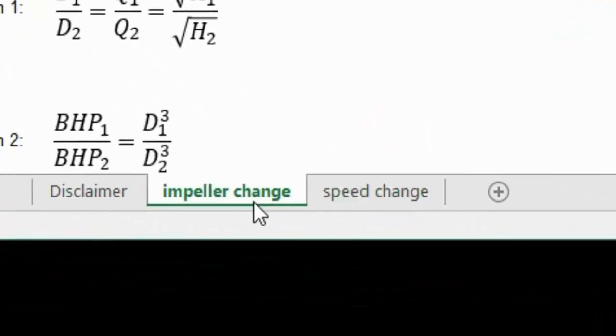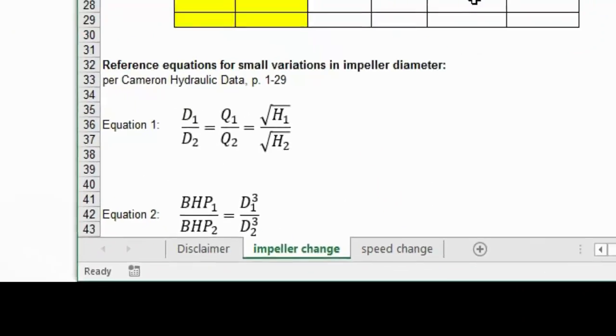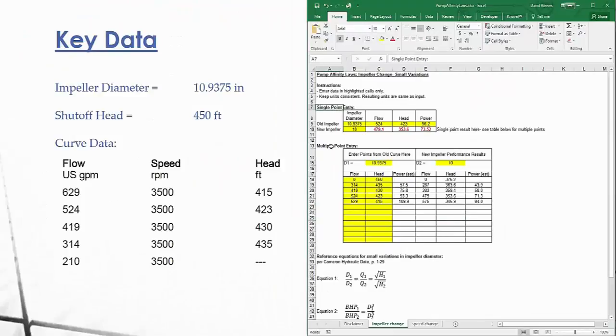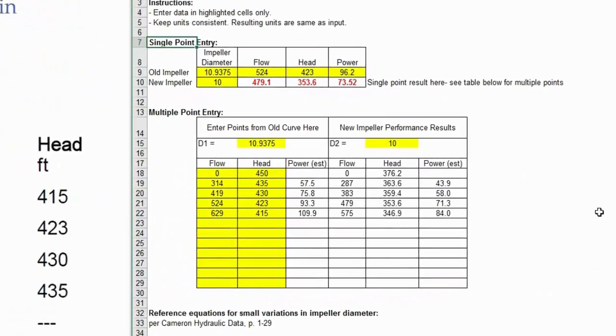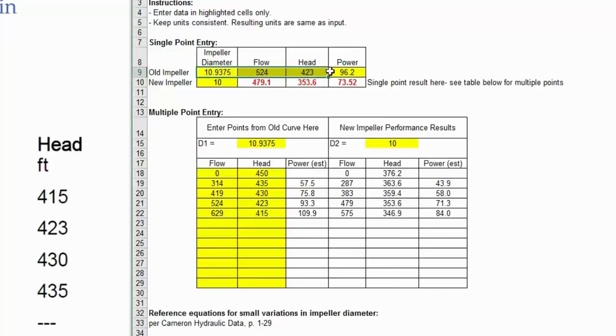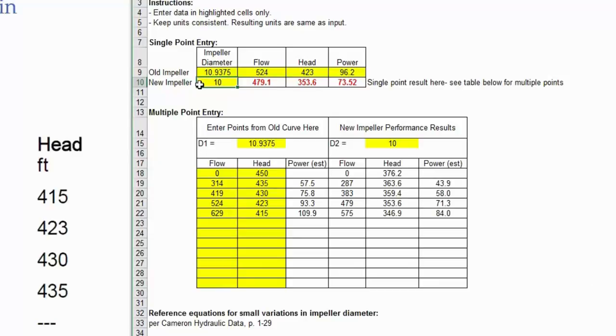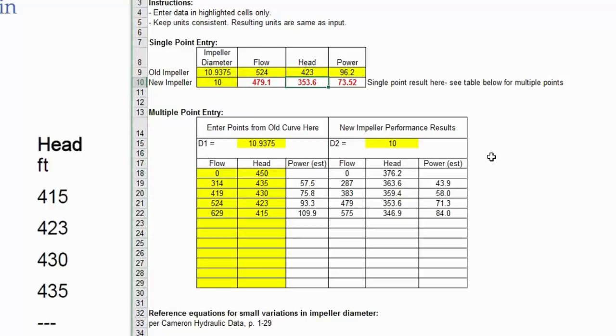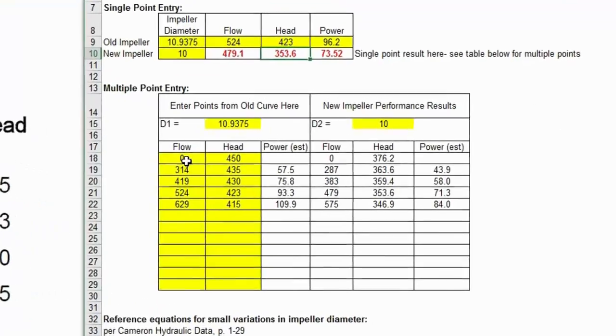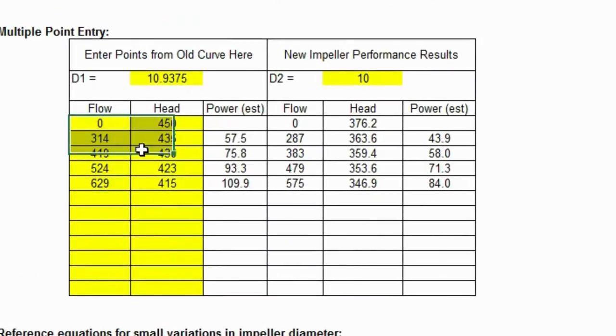They look similar. Both spreadsheets have a single point entry and a multiple point entry. Single point entry if you're just interested in one point on the pump curve. In our case, I already put the data in here just to save time. The yellow cells are the input cells. This was our initial data for the impeller diameter: flow, head, and power. Say we wanted to trim that impeller down to 10 inches. If you wanted to do that, or if you just wanted to increment the impeller to come up with some flow that you're looking to get or some target head that you're after, you can trim that impeller and you can get an estimate with the pump affinity laws. If you did trim the impeller and you want to know what the whole curve is going to look like, you stick your whole pump curve in here.